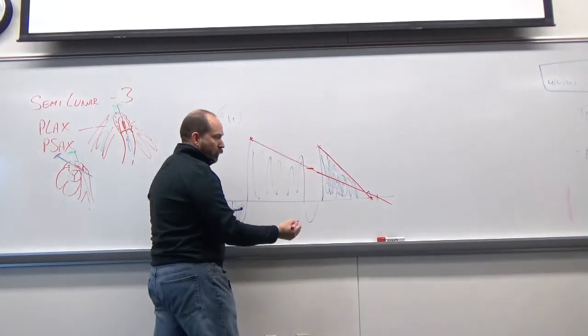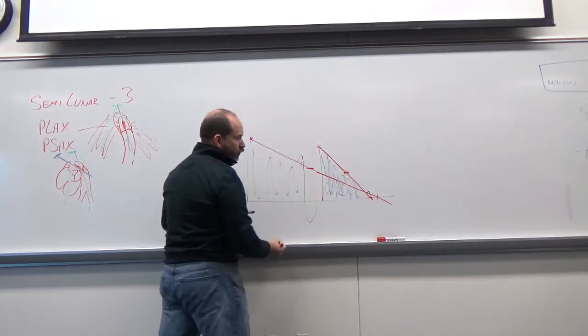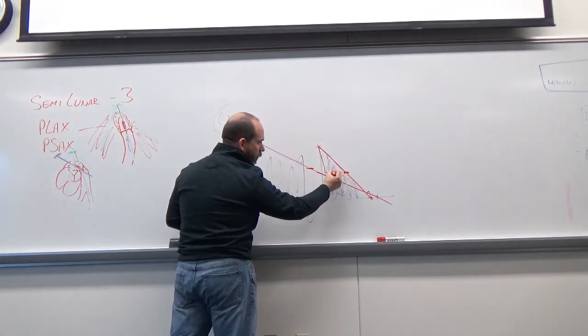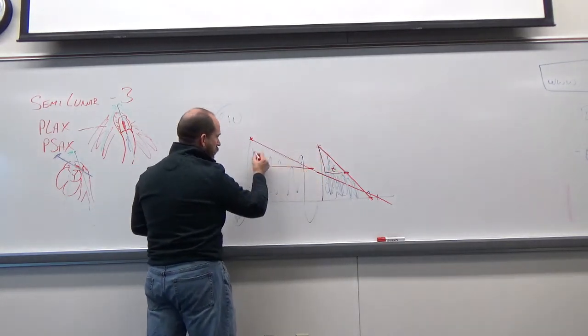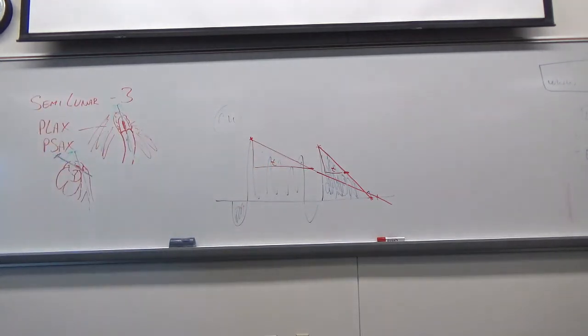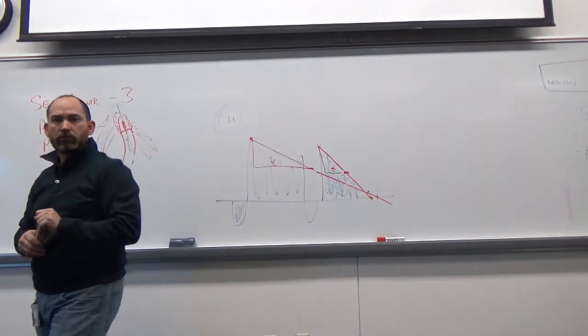That would be my pressure halftime there. This one, that's where it drops in half. But it's really looking at the time that it takes to do that, so the time is that x-axis there. As you can see, on a worse valve, this takes less time.